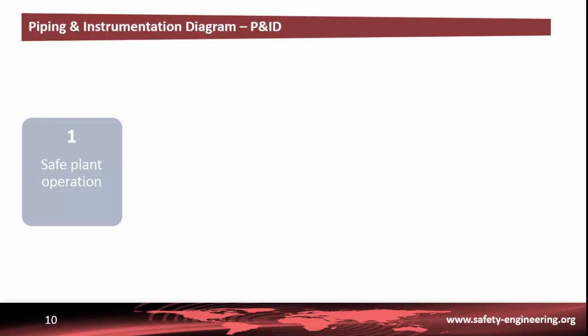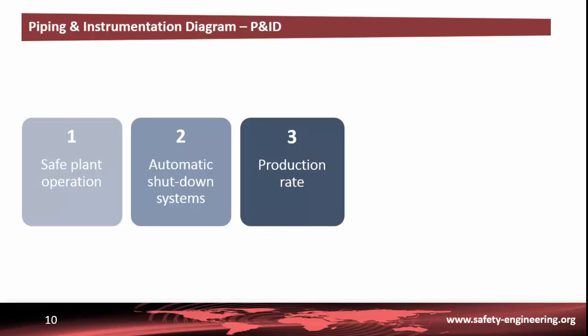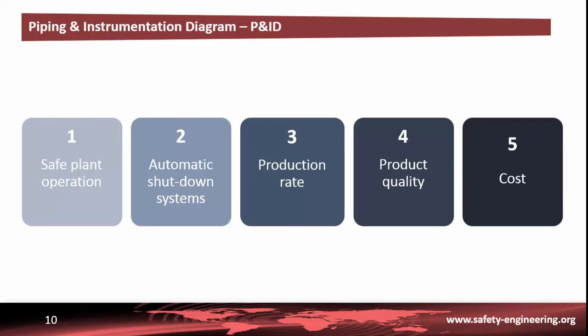Contrary to the PFD diagrams, P&ID diagrams show the various control loops and instruments in detail, with an identification number. The primary goals of the designer when specifying instrumentation and control schemes are: first, to keep the process variables within the known safe operating limits; second, to detect dangerous situations as they develop and to provide alarms and automatic shutdown systems; third, to provide interlocks and alarms to prevent dangerous operating procedures; fourth, to achieve the design product output and to maintain the product composition within the specified quality standards; and finally, to operate at the lowest production cost commensurate with the other objectives. These are not separate objectives and must be considered together. The order in which they are listed is not meant to imply the precedence of any one goal over another, other than that of putting safety first.